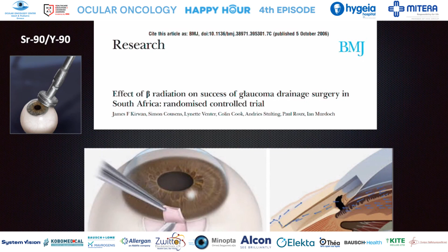However, we have improved delivery by adding shielding behind and lateral to the LV-Y90 disc. By eliminating strontium-90, the use of single-channel yttrium-90 purifies and thus simplifies radiation dose calculations. Y90 is what my engineers call short throw. As you see, the dose is concentrated at the sclera and mostly absorbed within millimeters as it enters the eye. For treatments like trabeculectomy, the lens would be relatively spared.